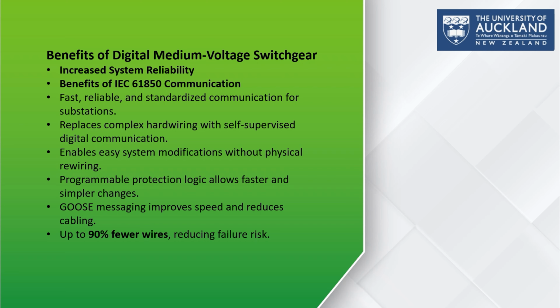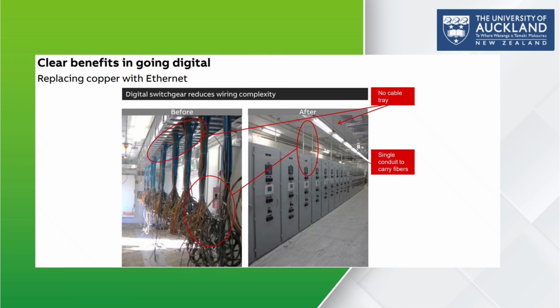So if you look at the before picture on the left, you can see what traditional copper-based wire looks like. There are hundreds of cables coming down from the cable tray. Each signal needs its own copper wire, which means more material, more labor, and more opportunities for mistakes or failures. Now compare that to the after picture on the right. Here the cable tray is completely gone. Instead of large bundles of copper wires, we have a single clean conduit carrying fiber optic cables, right?